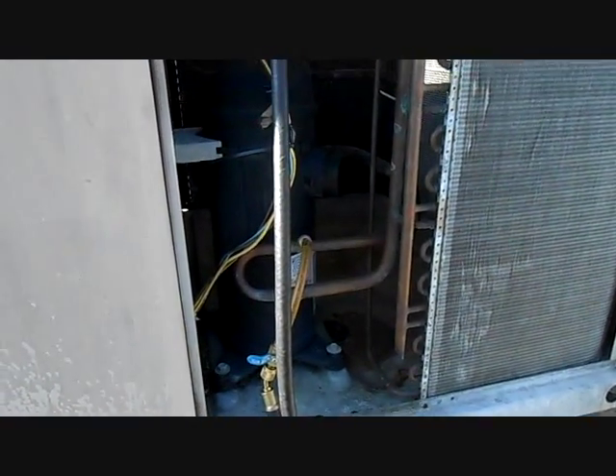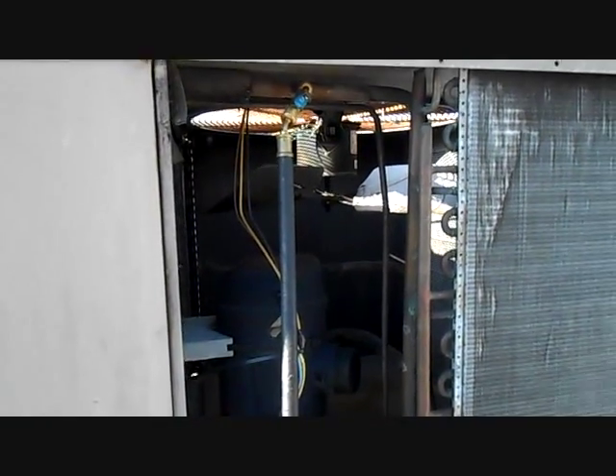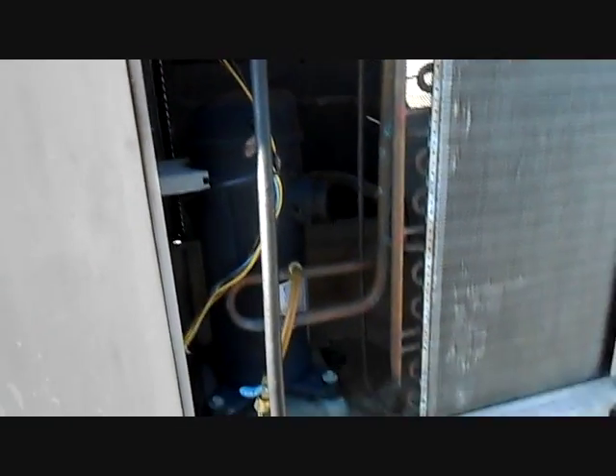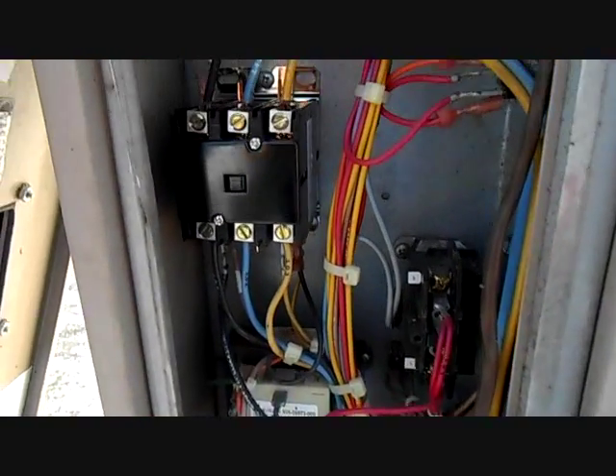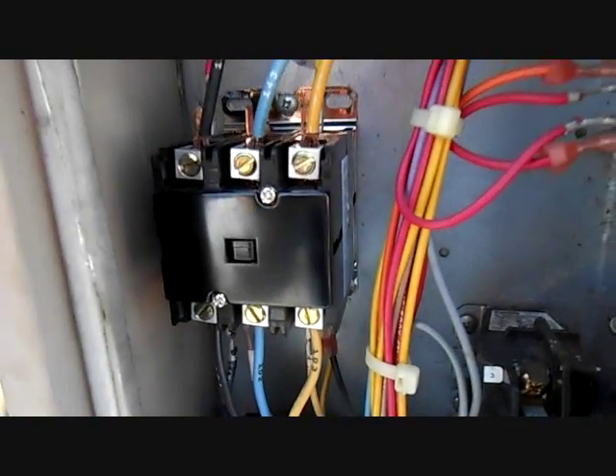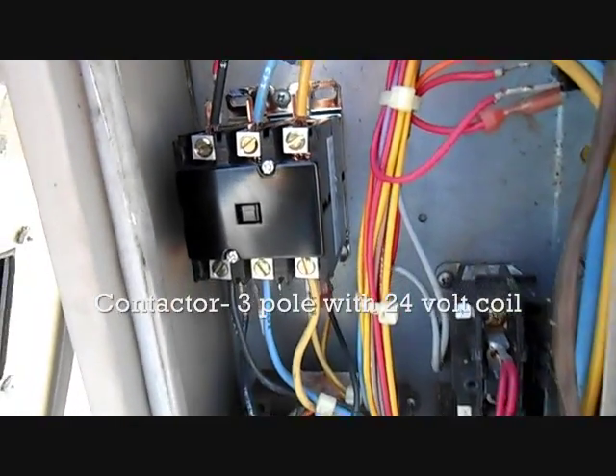I'm taking the charge out of here. Once I'm done, I'll put the old compressor out, put the old dryer out, and go ahead and make the changes necessary to make this functional. The power is now off to the machine — I was letting it run while we were doing some of the other stuff. I'm replacing the contactor here and also going to add something.